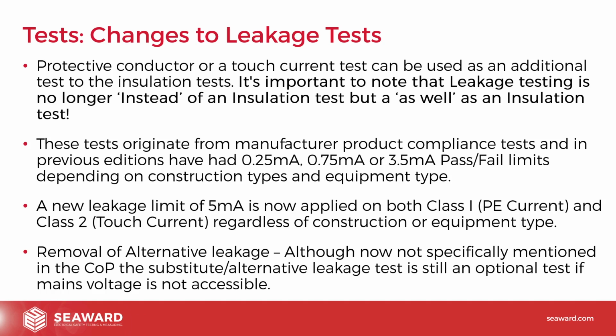So, in an aim to tidy up the code of practice and make it a bit simpler for most people to understand, there isn't now a specific separate reference to the alternative leakage test. Although it's not specifically mentioned in the code of practice now, the substitute alternative leakage test is still an optional test where you haven't got access to mains voltage, where you want to test on battery and you want to do a leakage test.